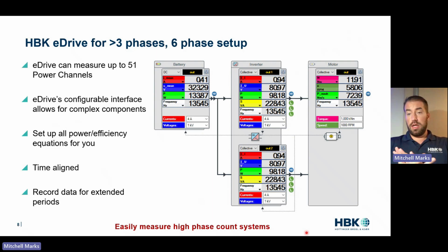For greater phase counts, and this is a little bit of an asterisk, the eDrive system does offer the ability to really easily add really high phase counts. So we can measure up to 51 power channels in one location. We have a nice software where you can set up multiple inverters, high phase count inverters, and graphically see that. So within one box, we can take all those phases. We give you really nice software to view that, and we set up all the power equations in the background. So you don't end up time aligning systems. You don't have to set up your own equations. So you can really easily measure these high phase count systems.